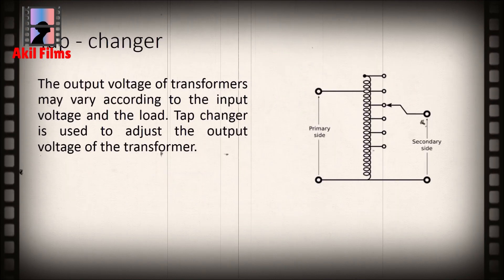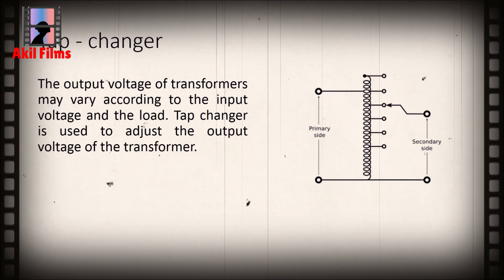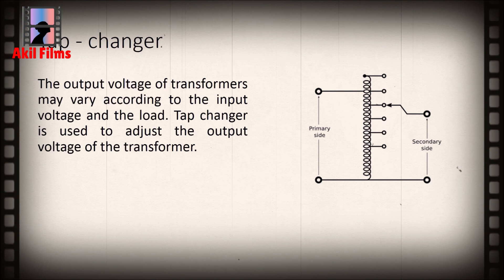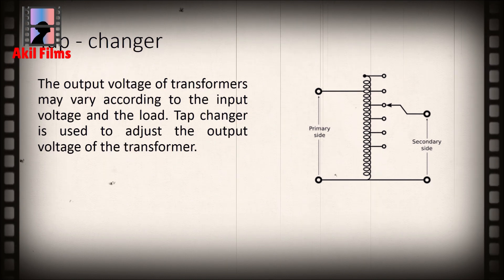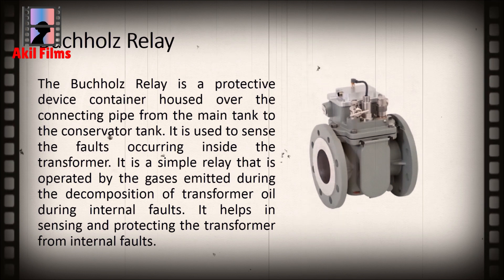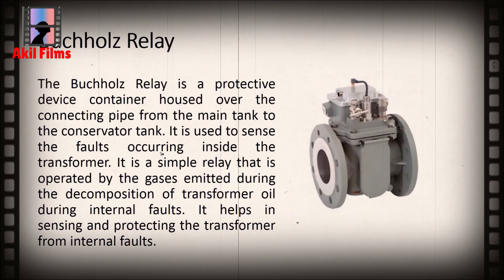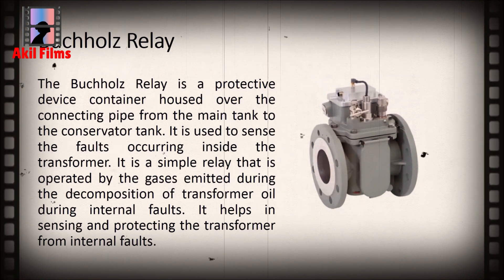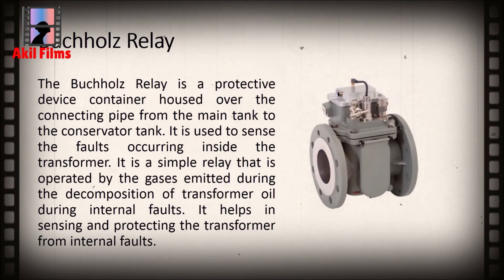The output voltage of transformers may vary according to the input voltage and the load. The tap changer is used to adjust the output voltage of the transformer. The Buchholz relay is a protective device housed over the connecting pipe from the main tank to the conservator tank, and it is used to sense faults occurring inside the transformer.